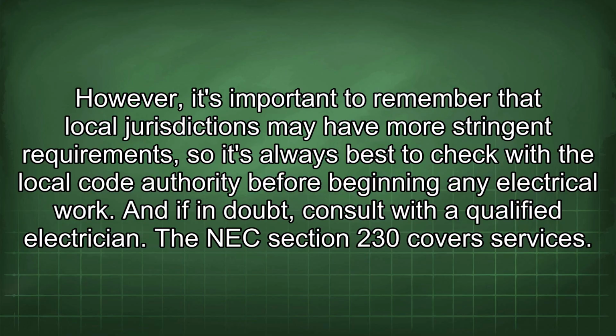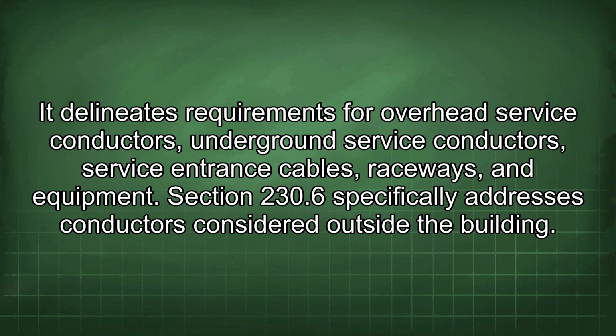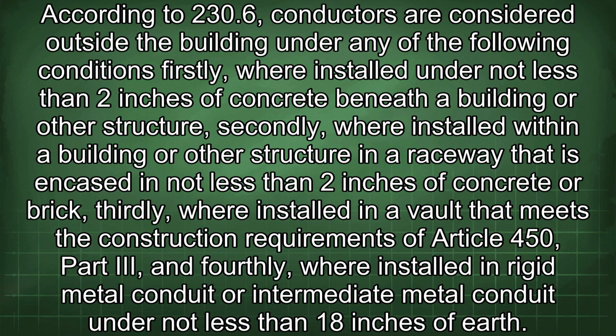The NEC Section 230 covers services. It delineates requirements for overhead service conductors, underground service conductors, service entrance cables, raceways, and equipment. Section 230.6 specifically addresses conductors considered outside the building. According to 230.6, conductors are considered outside the building under any of the following conditions.